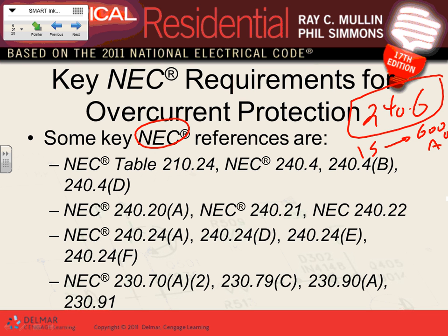So these, the limit, the number of circuit breakers you can do adjustable is unlimited, because you can adjust them based on the manufacturers. The non-adjustable ones, the fixed ones, they go from 15 all the way to 6,000, and in between 15, 20, if you guys remember, 25, 30, and so forth.